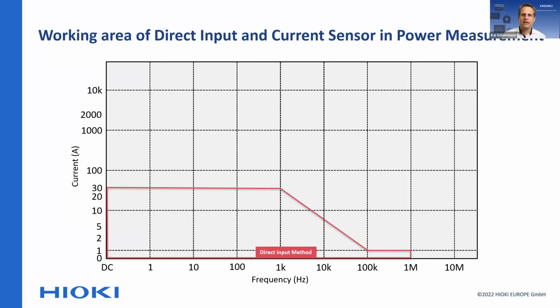The important part is comparing these for power measurement. We've seen that some sensors can go very low with current, but they're not necessarily suited for power analysis. Looking at power measurement, you can see clearly that nothing beats the shunt at very low currents.